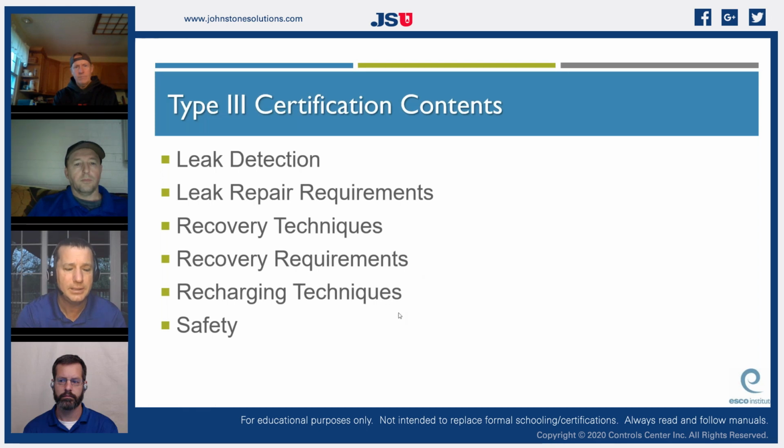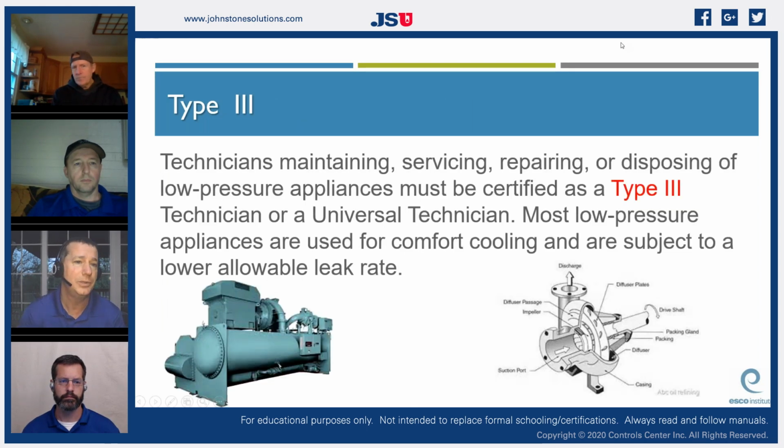Some of the things we're going to cover today are proper leak detection, leak recovery requirements, repair requirements, and charging and safety techniques, because they have some different aspects. Technicians who are maintaining, servicing, repairing, or disposing of low pressure, not necessarily low temperature, appliances must be certified as a Type 3 technician or a universal technician. Most low pressure appliances are used for comfort cooling and are subject to a lower allowable leak rate.